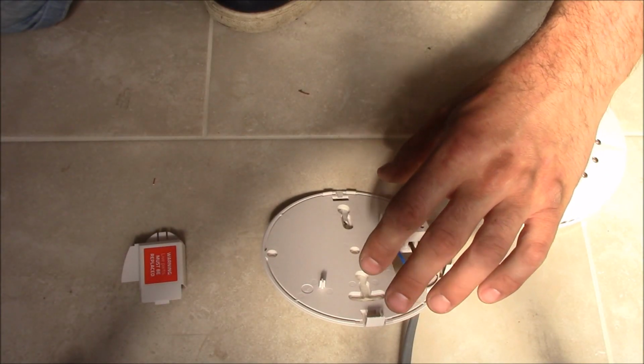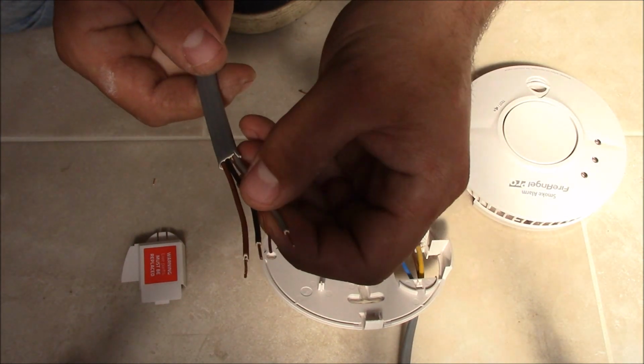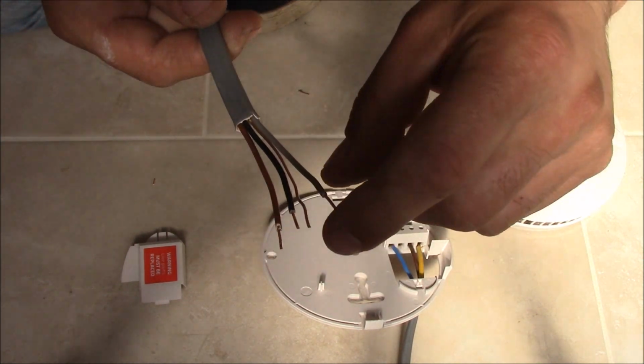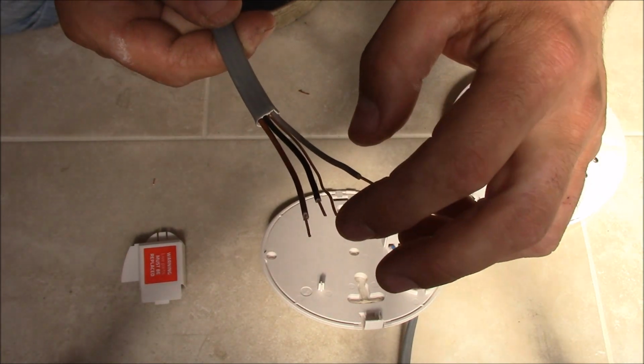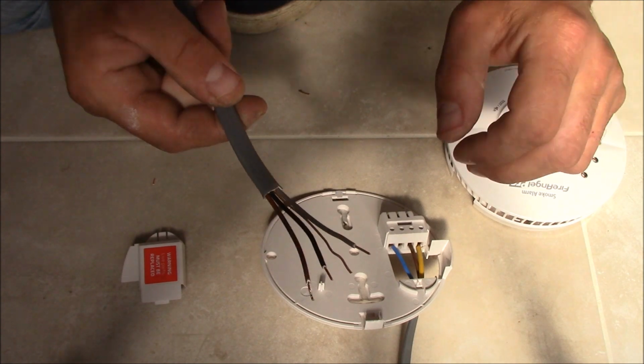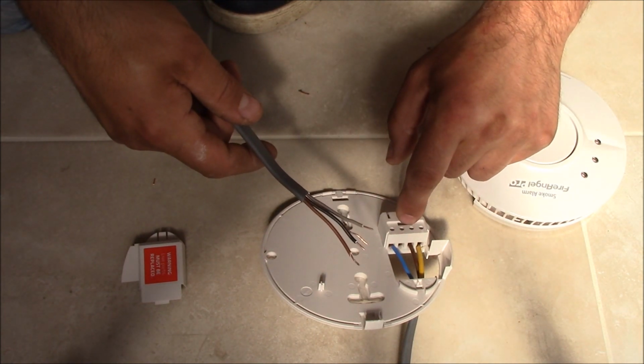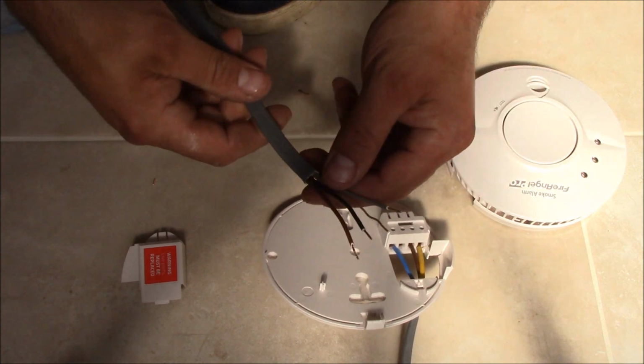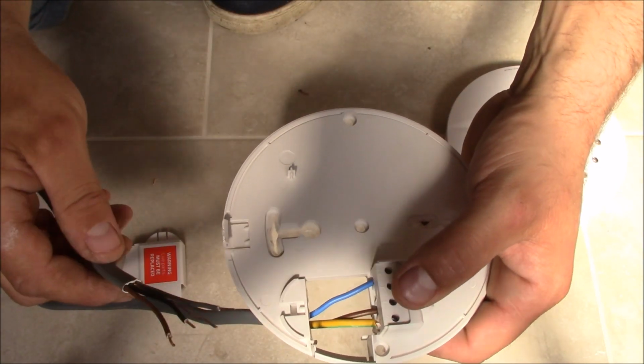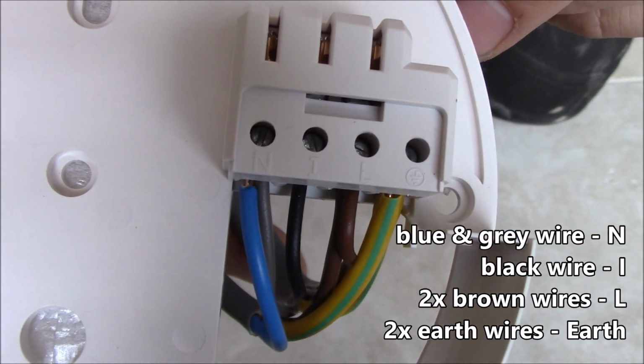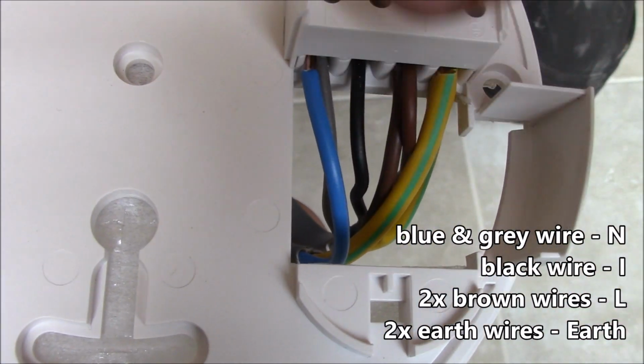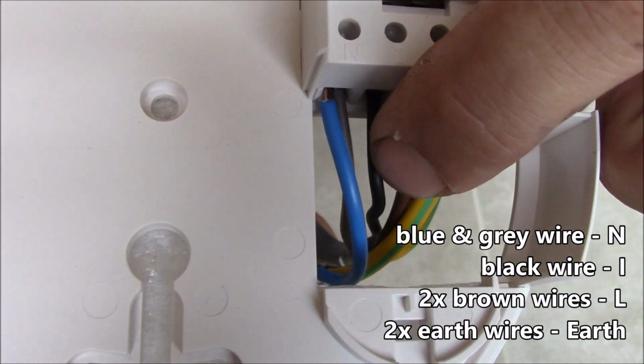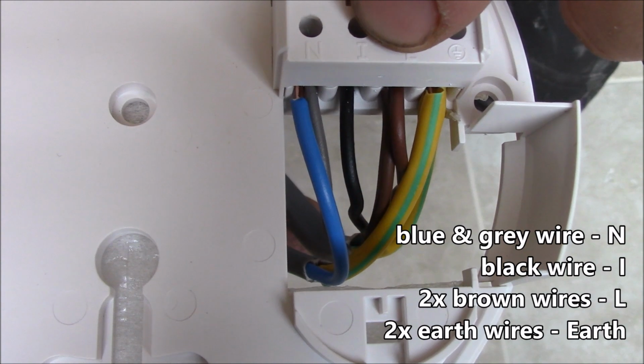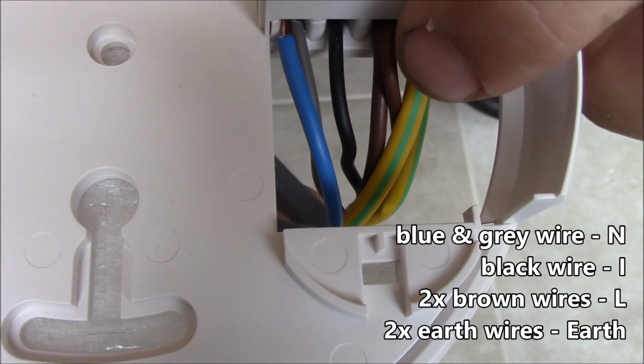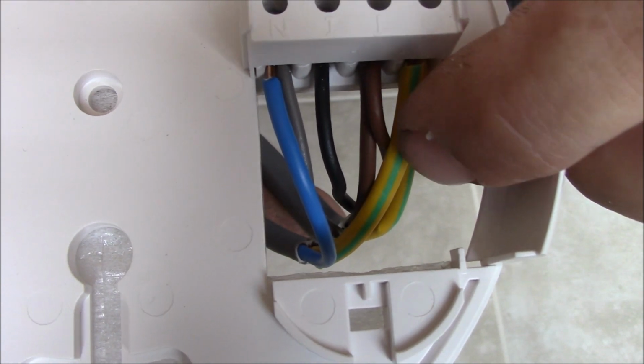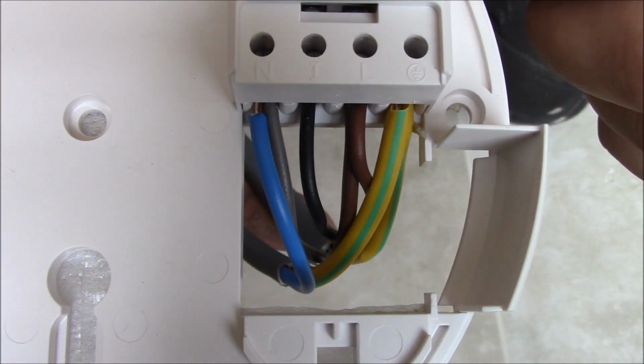So now if you want to interconnect this smoke alarm with another one the same, then you use 3-core and earth 1mm cable. It looks like this. The colors are a bit different. You put it into the same terminals along with these wires. And I'm going to show you how. So that's how it should look. Blue and grey to neutral terminal, then black to interconnection terminal, 2 browns to the line terminal, and earthing to earthing terminal.